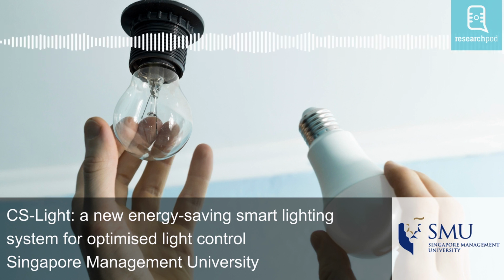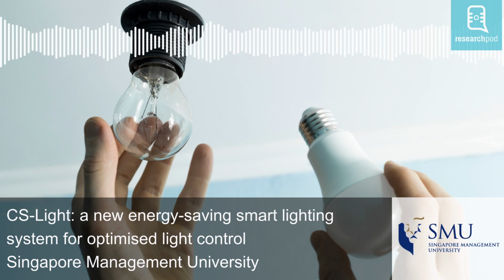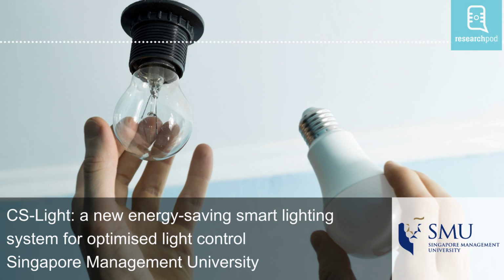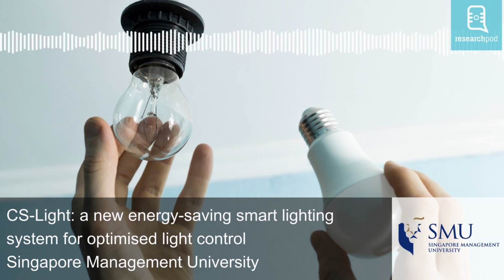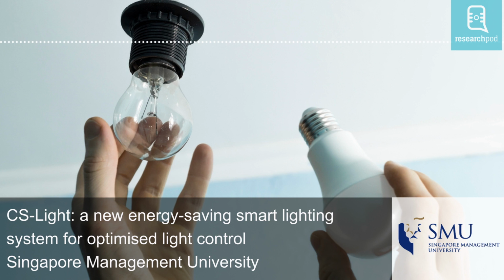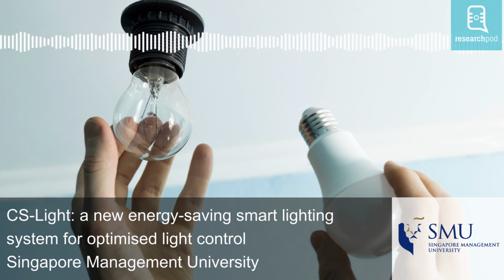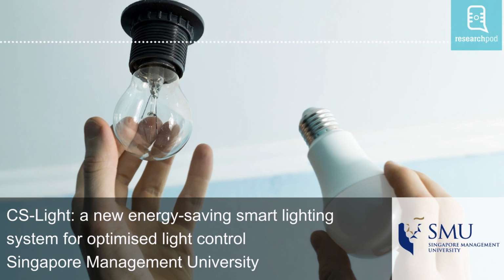Following this offline training phase, the researchers transitioned to the online or real-time phase for illuminance estimation with CS-Light. The first step involves image capture in real time, and then the identification and localization of human occupants in various workspace zones. The researchers then used micro-regions from images to estimate illuminance values using the ML models for color estimation and pixel-to-lux mapping mentioned earlier.